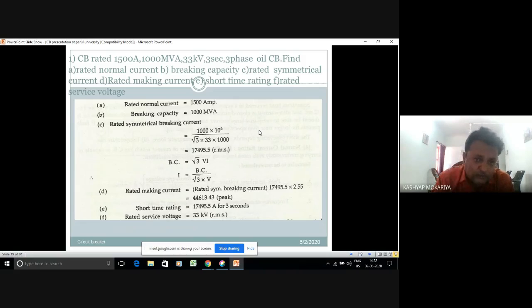So suppose the rated normal current is 1500 ampere, and breaking capacity is 1000 MVA. So I get the symmetrical breaking current. By multiplying it by 2.55, I get the peak making current. Remember that for the making current we always have to consider a peak value. Short time rating means for how long the rated symmetrical breaking current can be withstood. So suppose it withstands that symmetrical breaking current for 3 seconds, then it means that the short time capacity of the breaker is 3 seconds. And obviously the rated service voltage is 33 kV.